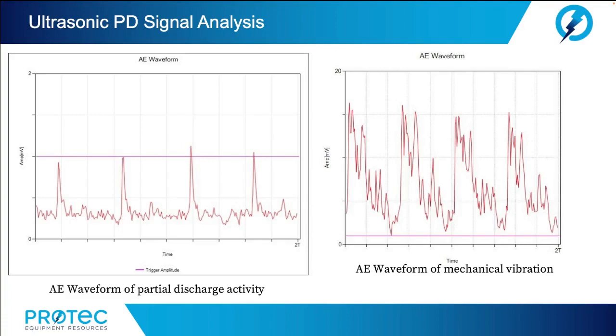Acoustic emission, or AE amplitude, is also used to compare the 60 Hz and 120 Hz resonance. If the 60 Hz resonance is approximately equal to the 120 Hz resonance, then the signal is most likely vibration or disturbance. A phase spectrum mode is also used to compare the incoming signal to the power frequency. It's like phase resolve PD patterns for UHF and HFCT testing. Vibration signals will have very consistent timing in sync with the phase and very consistent amplitudes. The peak amplitude will be very close to the average amplitude.